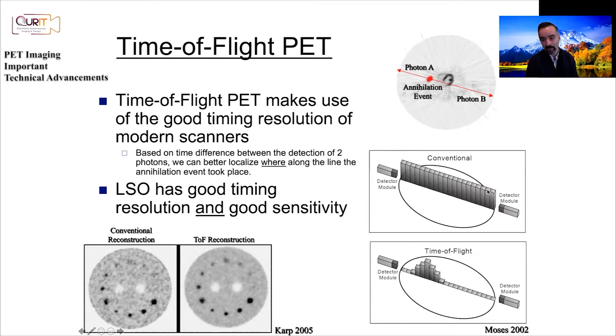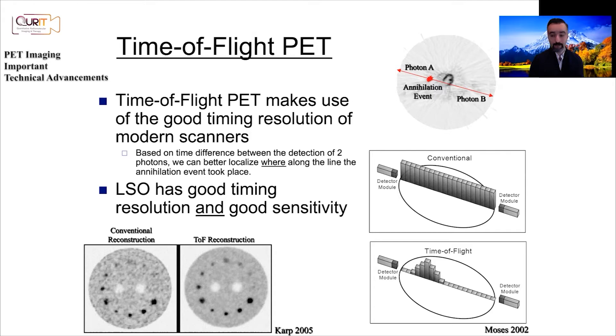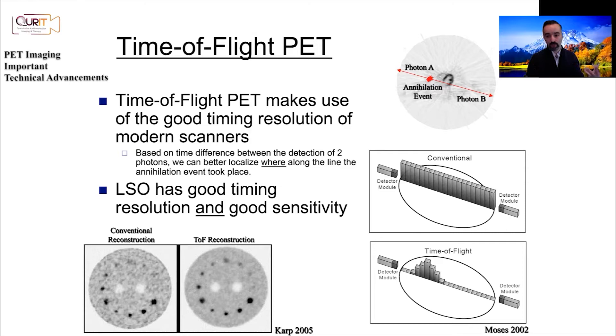Even without time-of-flight, when you surround the patient with detectors you can do tomographic image reconstruction and get good images. But when you do time-of-flight, your uncertainty along the line of response goes down, so instead of back-projecting along the entire line of response you back-project over a shorter region. This means you propagate noise less. LSO, for example, has been able to achieve this.